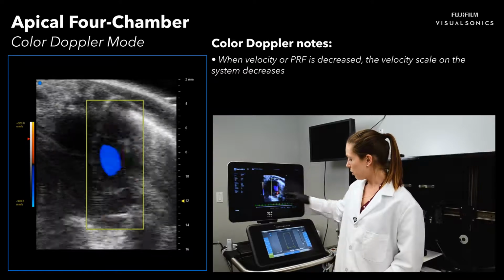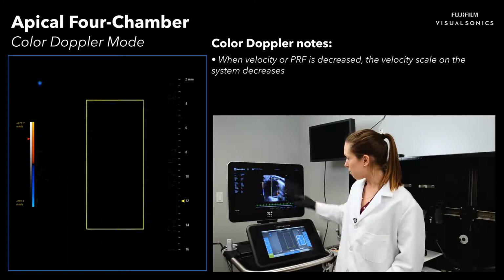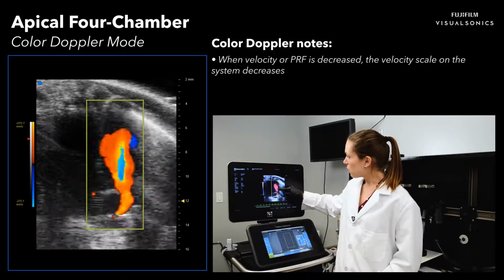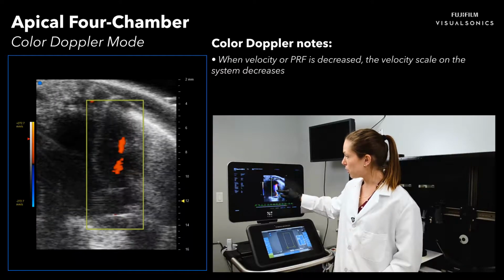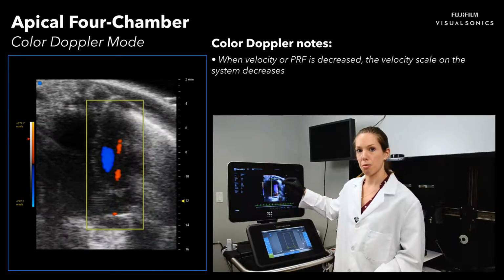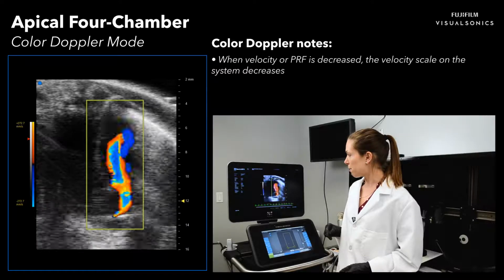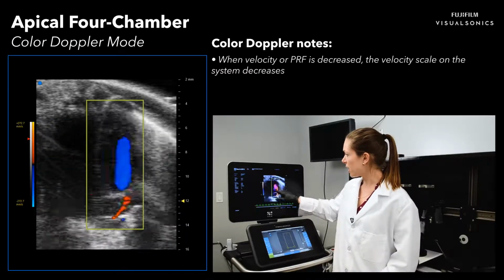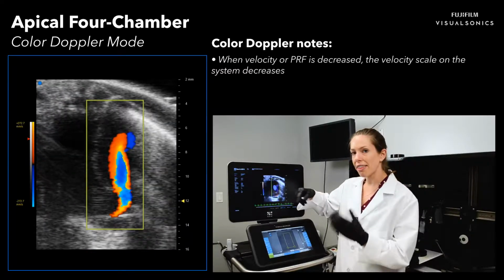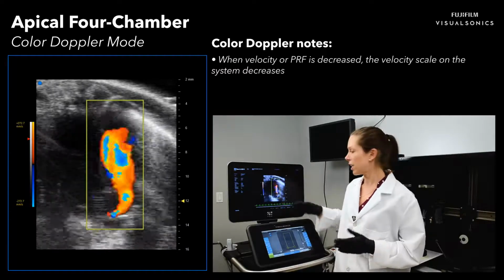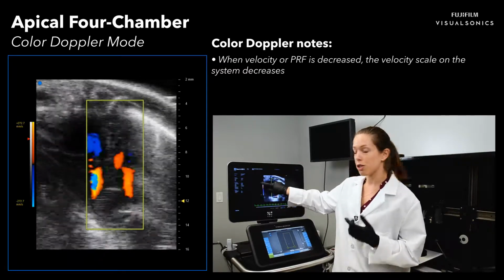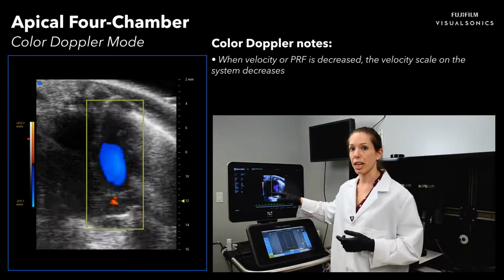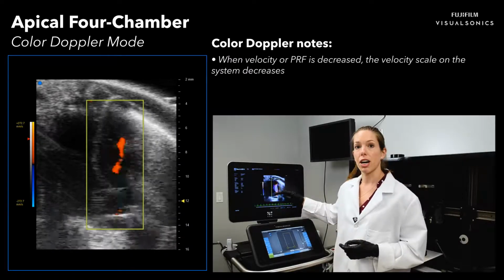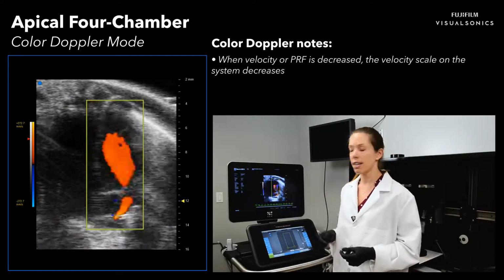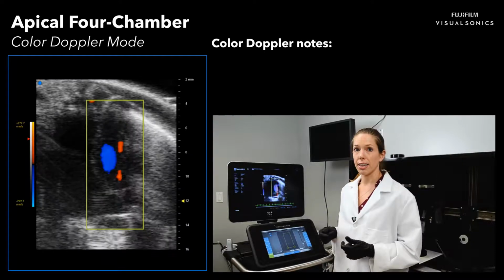And right away, you can see changes in what the color Doppler signal looks like. All of a sudden, you see blue that shows up within the red area of the color Doppler signal. This is because the blood in that area, it's not that it's going all of a sudden in a different direction, it's that it reached, in this case, 272 millimeters per second, and it wrapped around the color wheel because it's going so fast. And that is called aliasing.